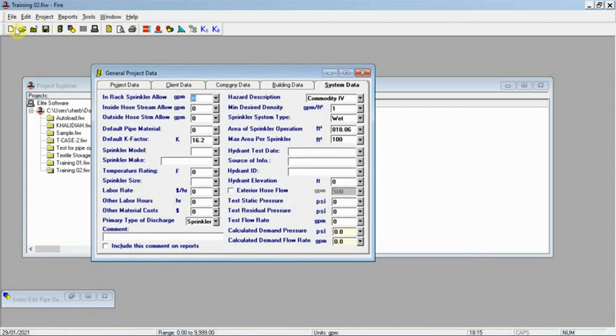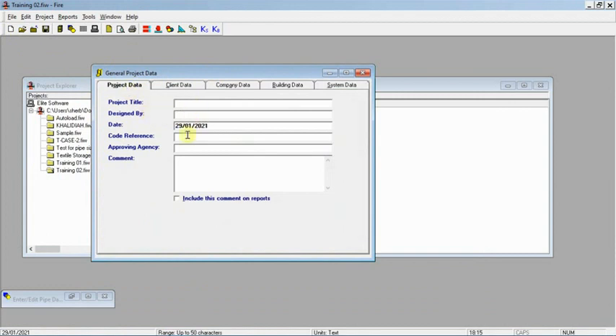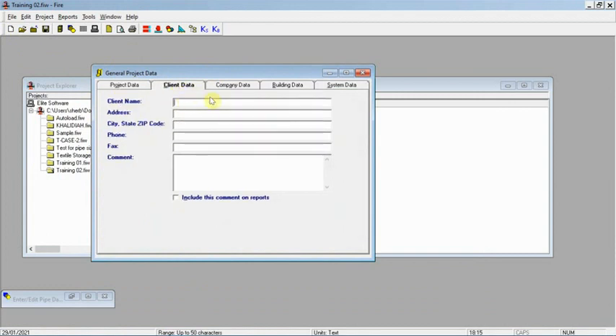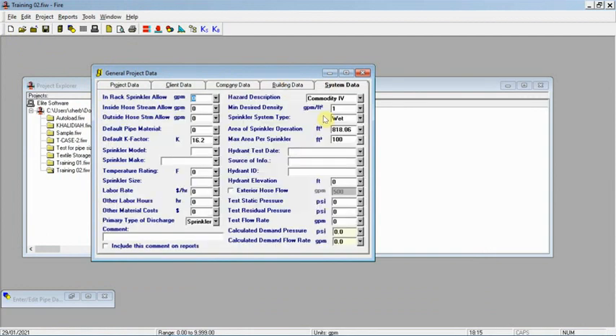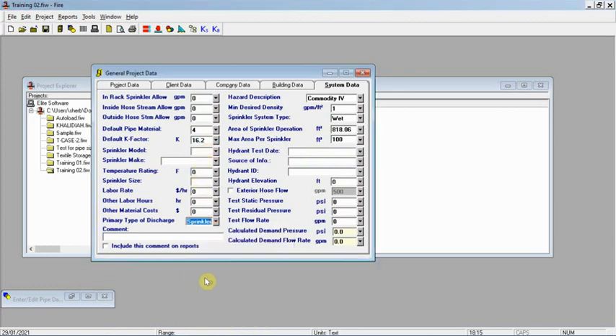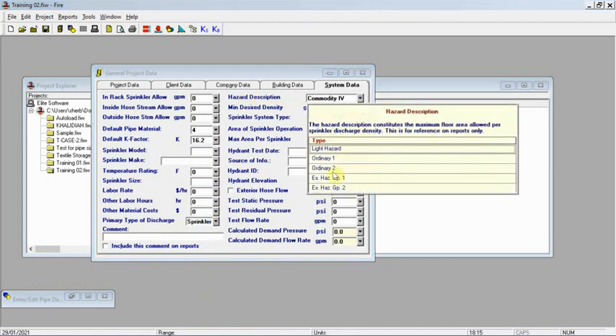Once you open the program, create a new project. You'll find the project data: project title, company data, building data — these are just for the final report. Go directly to the system data. The default pipe material we're using is schedule 40 black steel pipe. The default k-factor is 16.2; enter the sprinkler model if you have it.